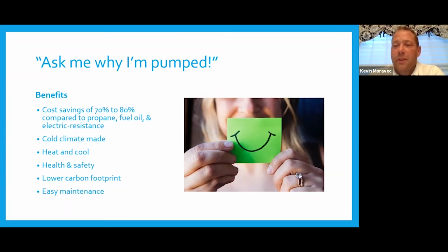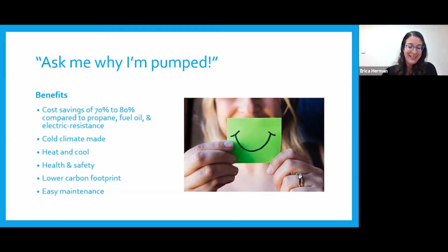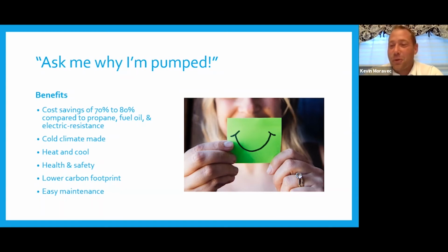One costs a little bit more, and the majority of that cost is tied up in the ground loop. In an example like Paul's, if he had to pre-buy 25 years of propane at his previous rate, he's spending $50,000 to $60,000 on propane at current rates. That ground loop pre-purchases all of the heating energy in that house for the next 300, 400, 500 years - as long as nobody decides to dig the garden up deeper than a backhoe can go, about 5 feet. That ground loop will exist there for a long time. And even if somebody does nick it, we can go fix it - it's not a big deal, it's just plastic pipe.